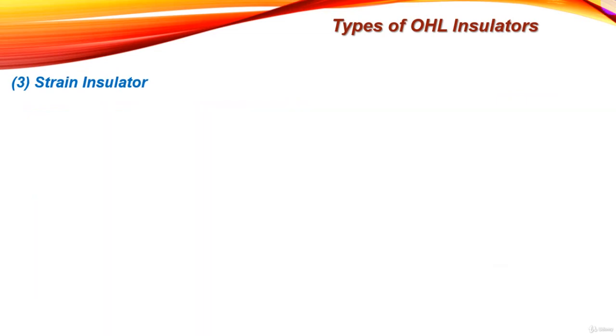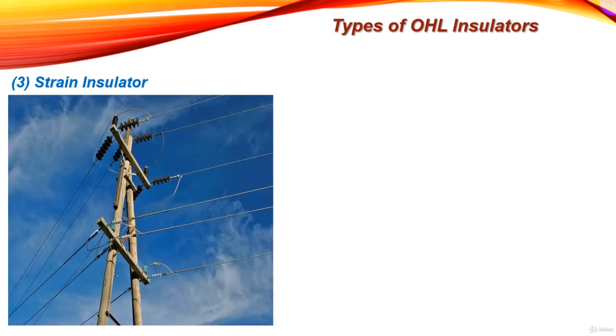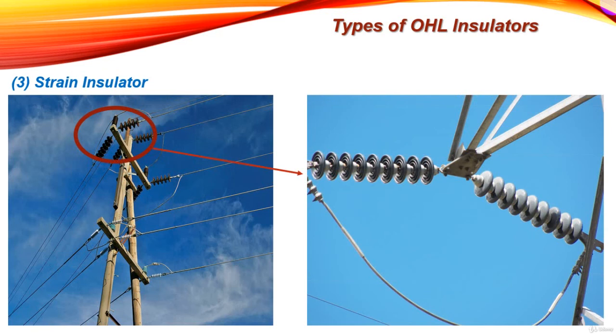The strain insulator is used when there is a dead end of the line, or there is a corner or sharp curve, where the line is subjected to greater tension. In order to relieve the line of excessive tension, strain insulators are used. They are specially mechanically strong suspension insulators, used to take the tension of the conductor at line terminals.